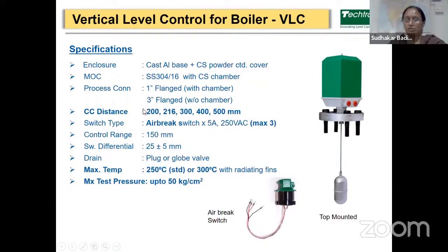The CC distances of the external chambers are available from 200, 216, 300, 400 or 500 mm. This is the standard one. Others can be available on request. The switch type is an air break switch, which is suitable for 5 ampere at 250 volt AC. Maximum three switches are available. The control range is 150 mm. It is suitable for maximum temperature of 250 degrees Celsius, or 300 degrees Celsius with radiating fins, and test pressure of 50 kg per centimeter square. Here you can see the top mounted VLC, and this is the air break switch of it.